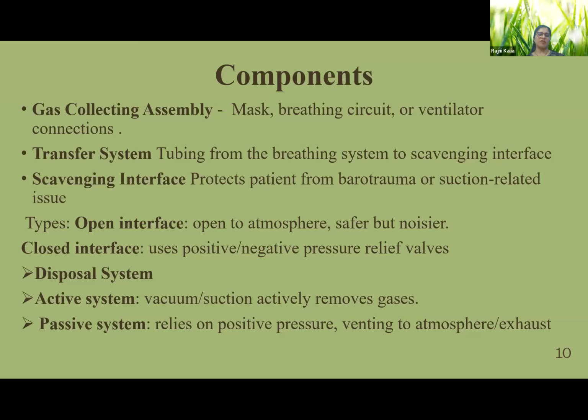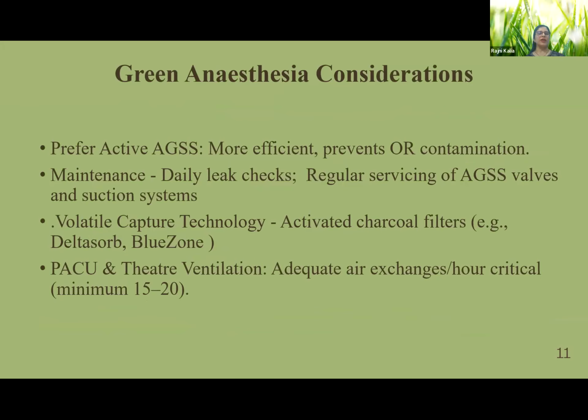Disposal systems can be active or passive. Active is preferred, as a vacuum or suction actively removes gases, whereas passive relies on positive pressure for releasing the gases. The green anesthesia considerations will be for these.